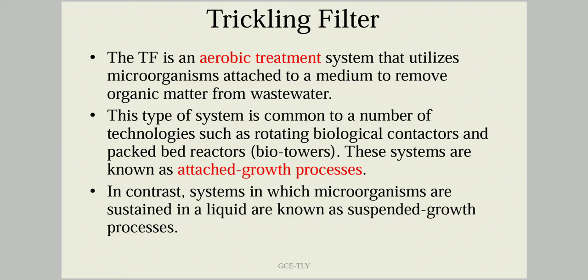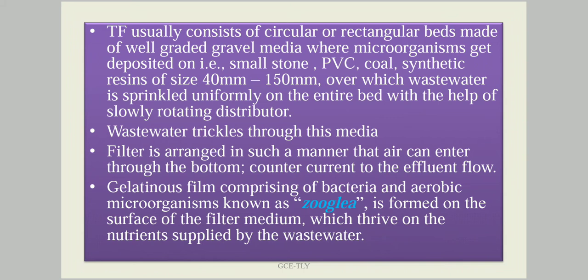In contrast, there are other systems where microorganisms are suspended in liquid, known as suspended growth processes. Trickling filtration usually consists of a circular or rectangular bed made of well-graded gravel media on which microorganisms get deposited and grow. This gravel media may be small stone, PVC, coal, or synthetic resin, with sizes varying from 40 mm to 150 mm. Water is sprinkled at a uniform rate over this media.